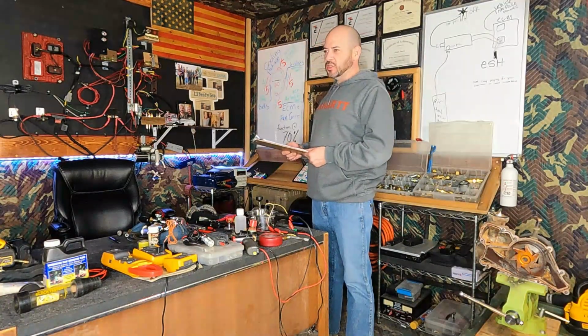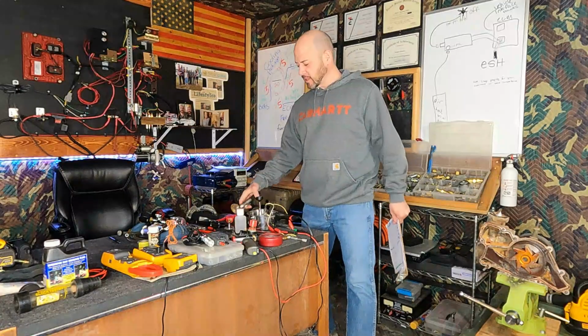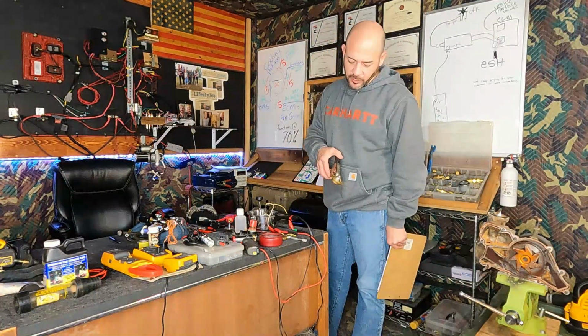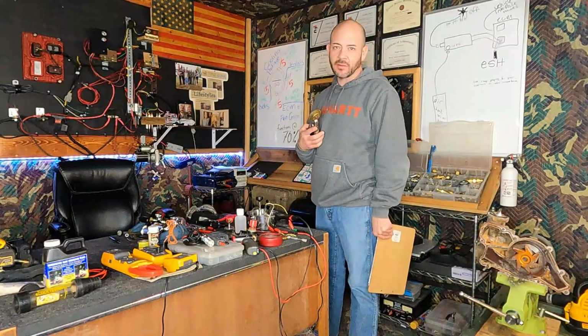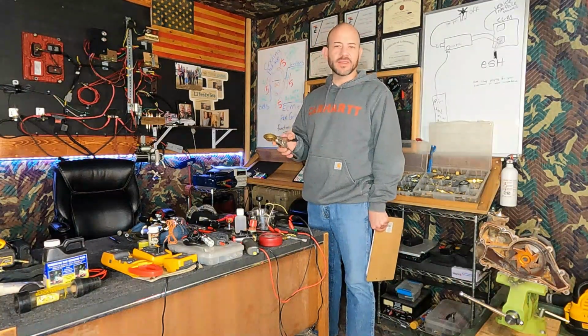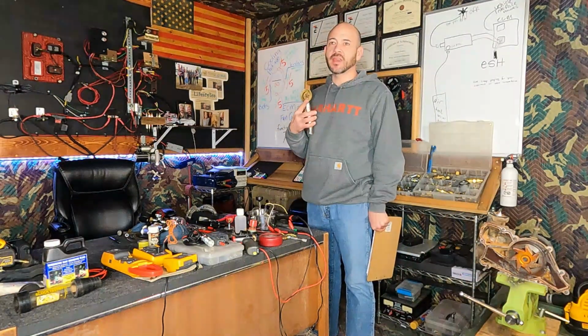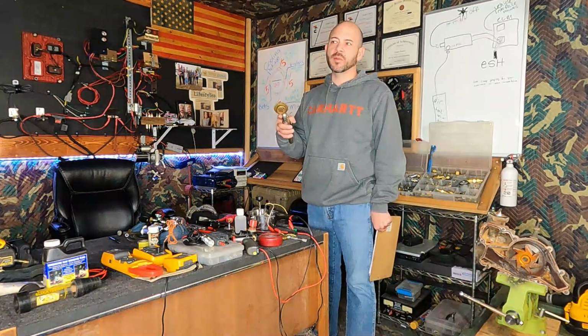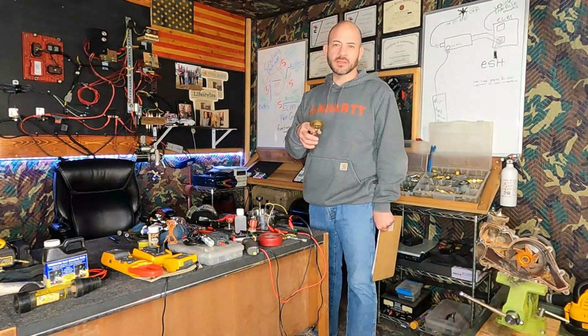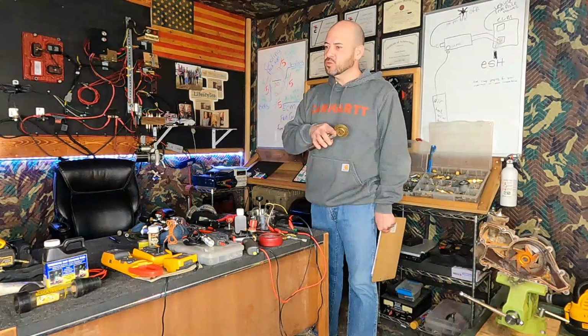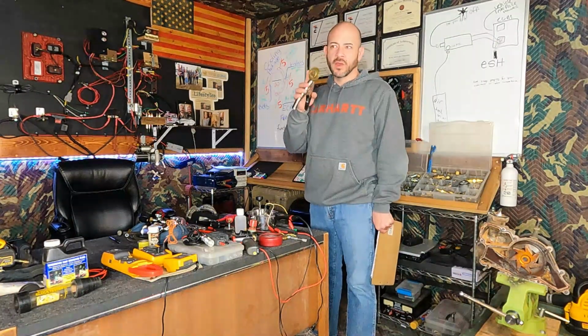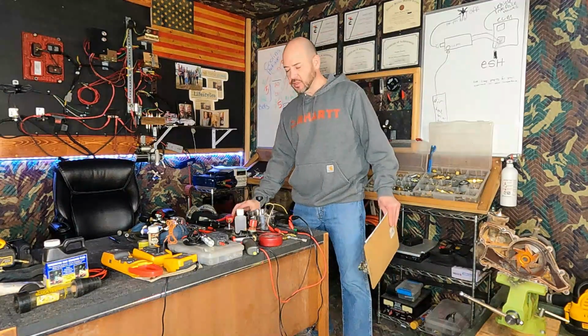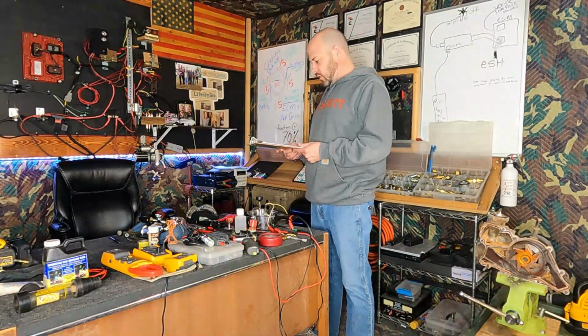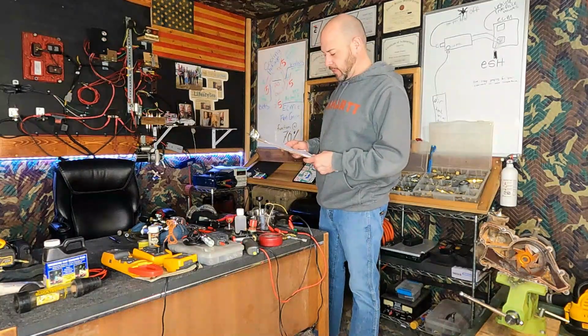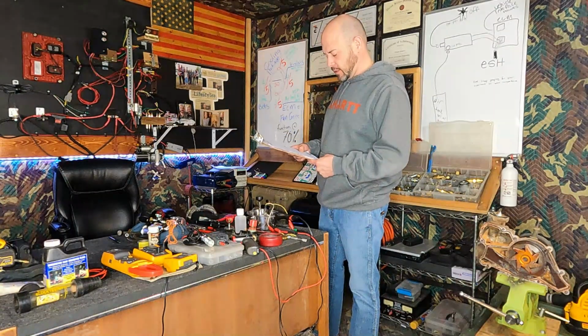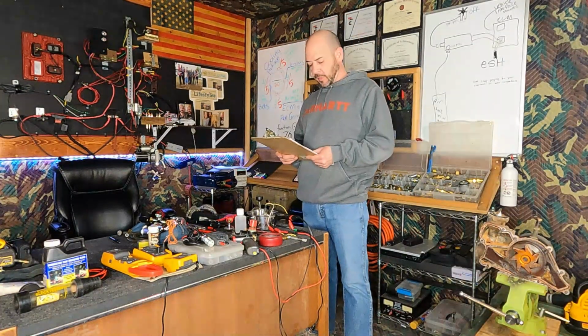So the thermostat's not open just a little bit. I can't say that enough because I've seen thousands and thousands of dollars spent because they say I just replaced the thermostat. That doesn't matter, I need to test everything. If you have a problem standing before me, you can't tell me what you replaced, because I see people replace things with bad parts, used parts, and parts that fail quickly. If you're troubleshooting, you never, ever remove a new part from your equation until you've tested it. I'm going to go over this quickly, I'll wait until we get to temp sensors.